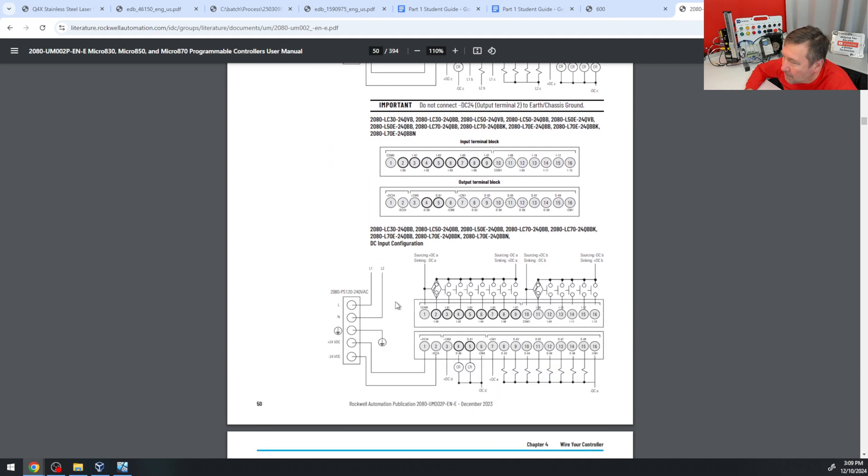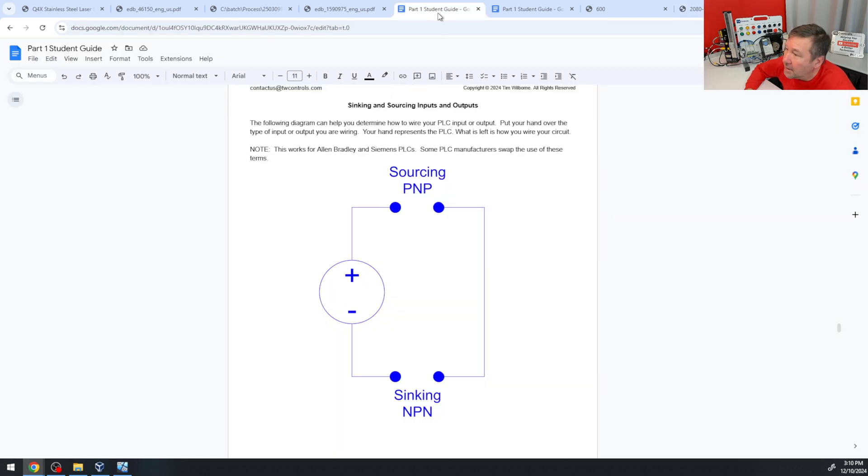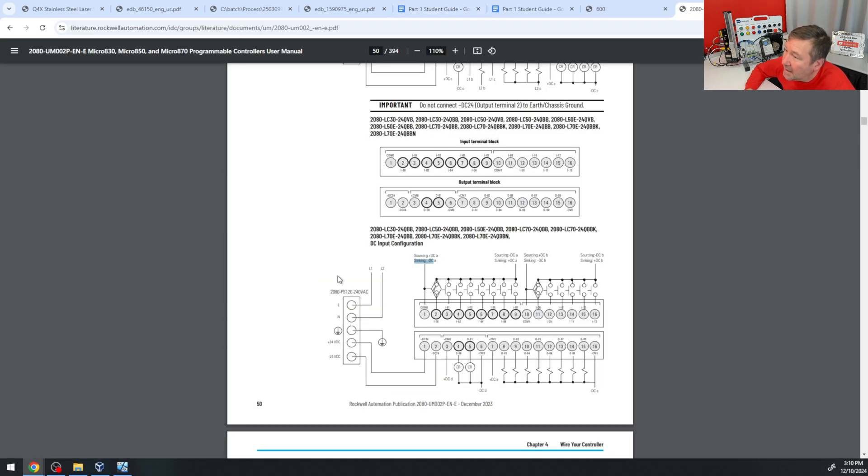But if we look down here, we get some examples. And notice it says here, sourcing plus DC goes to common, sinking minus DC goes to common. And so if we go back over here, we knew we had a PNP sensor, and that means we needed a sinking PLC input. And so we have a sinking PLC input.